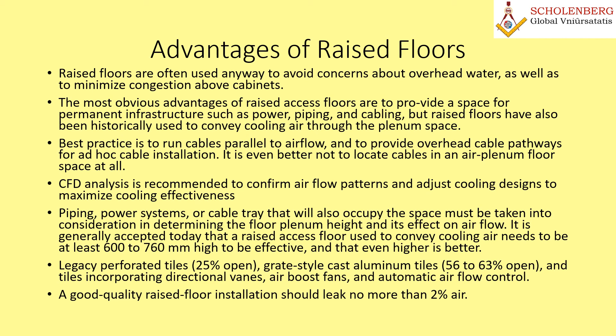Then there are directional vane type tiles. Then some tiles have an air booster fan fitted inside, and there's automatic airflow control also within. So these are all the modern technologies which are commonly used when you fix these tiles and whatever airflow you need. There are various types and varieties available in the market. A good quality raised floor installation should not leak more than 2% of the air as per the ASHRAE Handbook 2019 Applications. So this is also a very important factor, so it should be properly, tightly sealed.